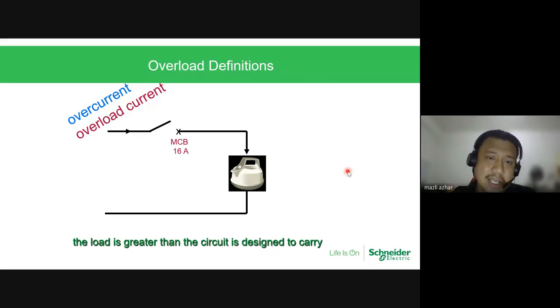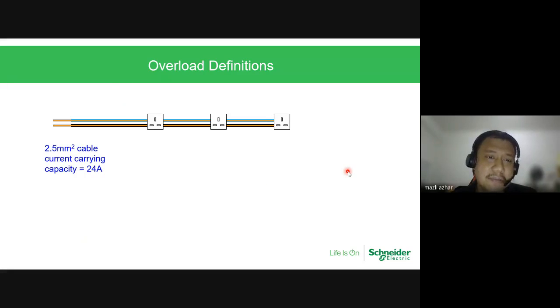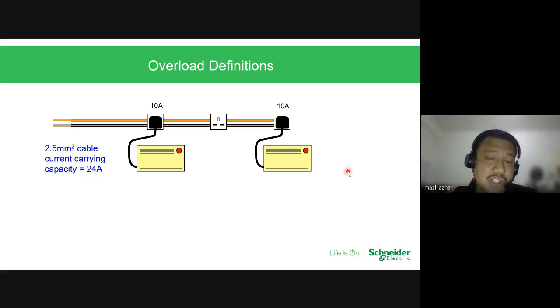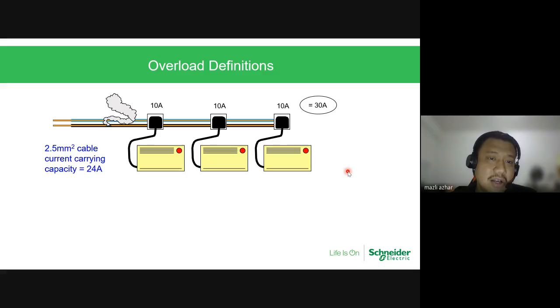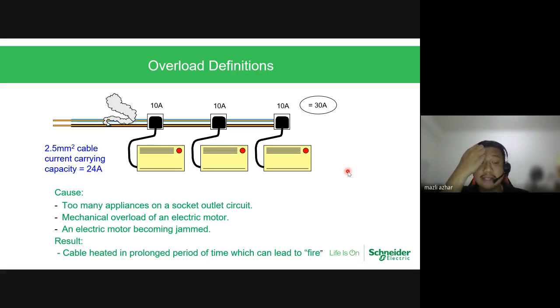So by definition, one MCB protects one kettle. When you add another load there, it exceeds the current rating. In simple terms, you have a 2.5 mm cable with a current carrying capacity of 24 amps. You have 3 sockets, but this is not protected by a breaker. You put a 10 amp load, should be no problem, right? Because it doesn't exceed 24 amps. You put another 10 amps, so the total is 20 amps, not exceeding the current carrying capacity yet, but you put another one, so it reaches 30 amps. So this is where overload occurs, whereby there are too many appliances.